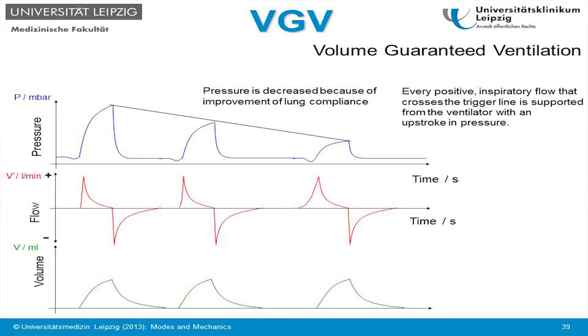A combination of pressure controlled and volume controlled ventilation would be volume guaranteed ventilation, where the ventilator monitors the expiratory tidal volume of the patient by using a flow sensor. And if the tidal volume is higher than the preset value, then the ventilator will reduce the pressure for the next breath. And if the tidal volume is still high, then the ventilator will reduce the pressure again. When the patient then becomes more difficult to ventilate, the ventilator can ramp the ventilator pressure up again in order to maintain a certain tidal volume. So this is for each breath. The pressure is pre-calculated by the ventilator.